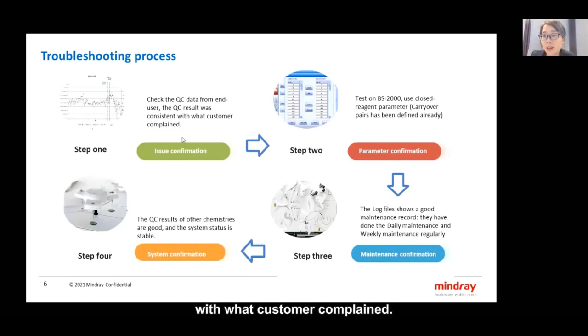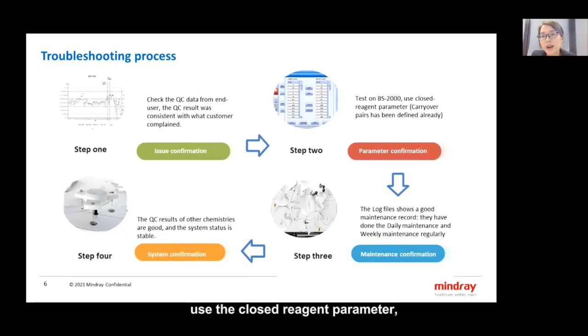As you can see, we did troubleshooting on this case. Firstly, we made an issue confirmation. We checked the QC data from the end user, and the QC result was consistent with what the customer complained about. Then we made a parameter confirmation. The creatinine test on BS2000 uses a closed reagent parameter, and the carryover pairs have already been defined. Next, we made a confirmation on maintenance. The log file shows a good maintenance record. They have done the daily and weekly maintenance regularly. Finally, we made a confirmation on the system. The QC results of other chemistries are good, and the system state is stable.